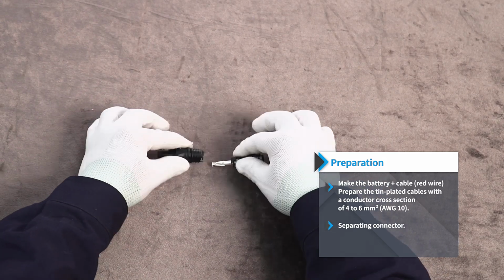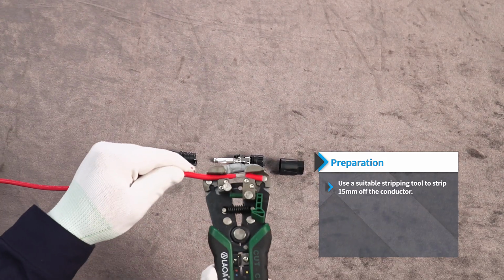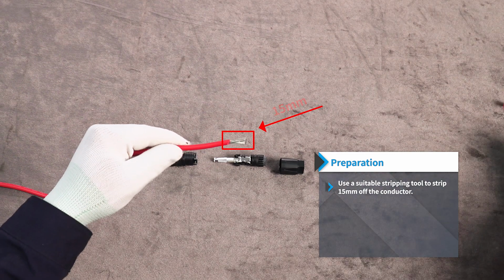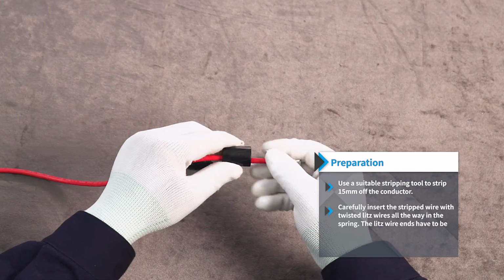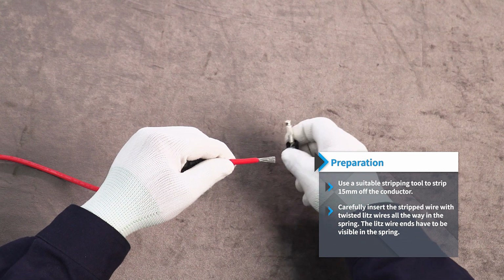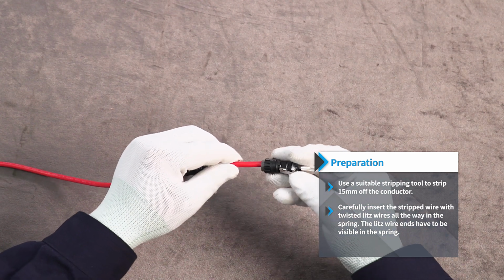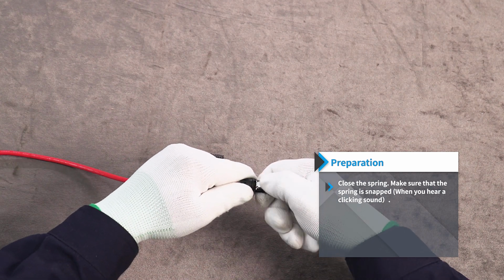Separating connector. Use a suitable stripping tool to strip 15 millimeters off the conductor. Carefully insert the stripped wire with twisted Litz wires all the way in the spring. The Litz wire ends have to be visible in the spring. Close the spring, make sure that the spring is snapped.